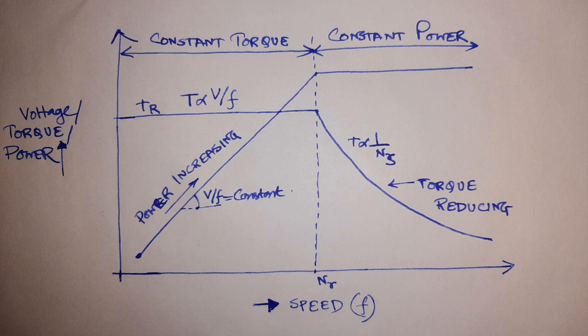That is its rated torque. In that region, if you increase the speed gradually keeping V/f constant, the torque will be constant and the power will gradually increase. Because we know that P equals omega times T.